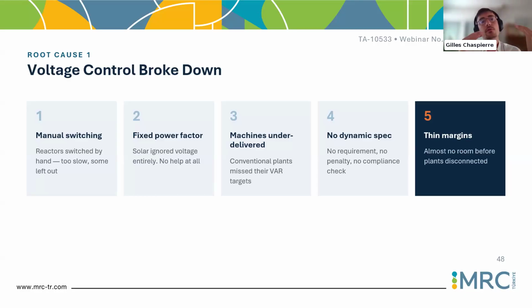You cannot tell the TSO you can operate transiently at that voltage level if at the same time you know that at that level some machines will trip. So this is what is behind this thin margin message. It's really important to have sufficient room to make sure that when you reach this high voltage, the machines that can allow you to decrease the voltage remain connected. So you need to either increase the protection settings or just say, and uniformize that across Europe, let's not operate any more at voltages up to 435 kV. For other European countries, it's most of the time 420, 425. Yes, next slide, please.